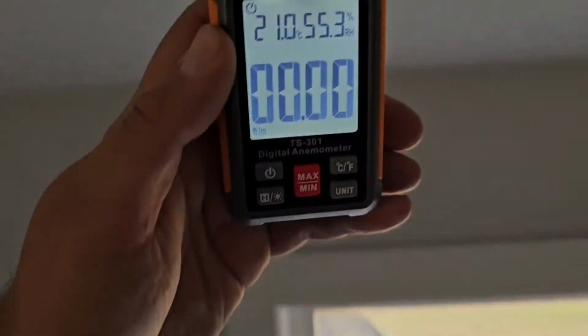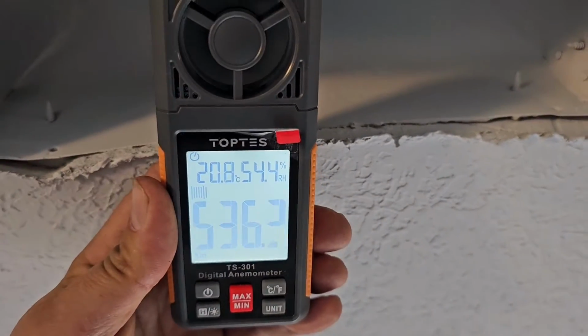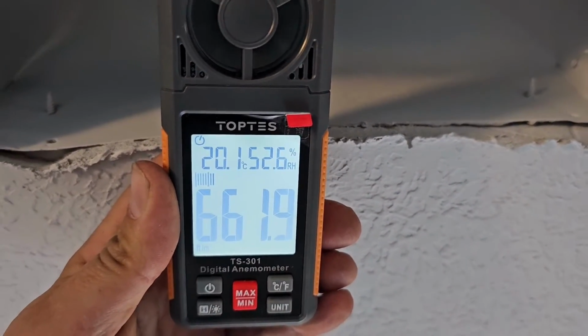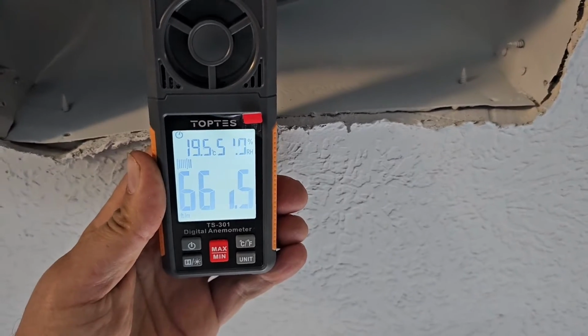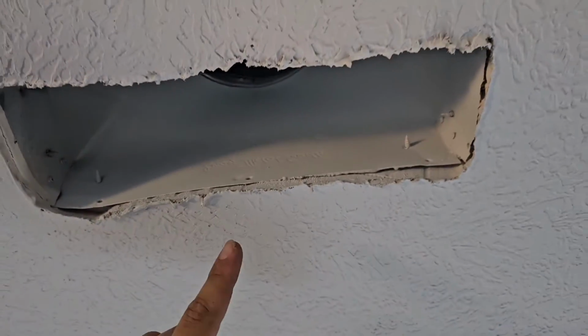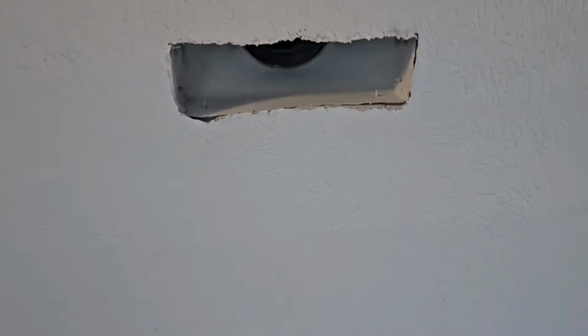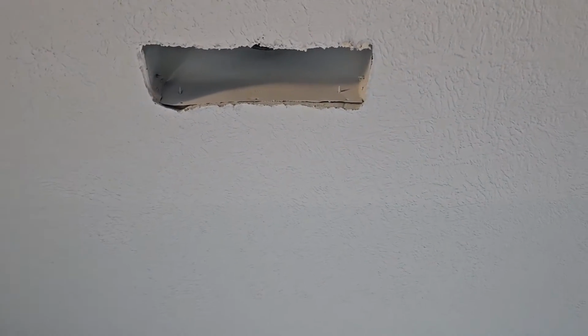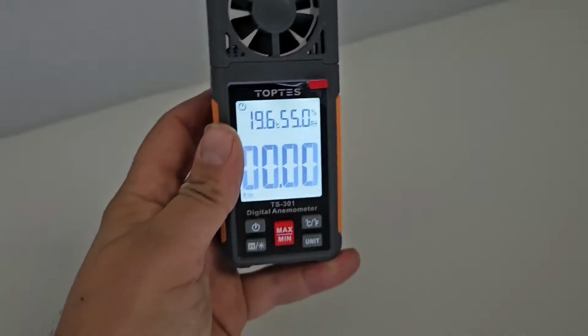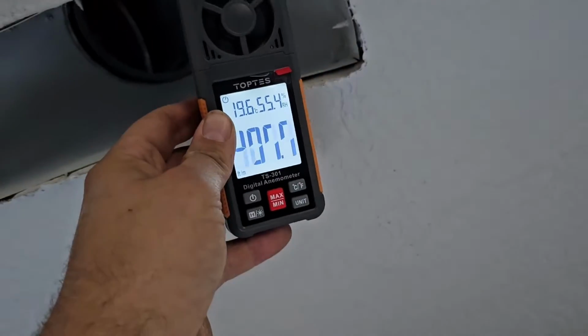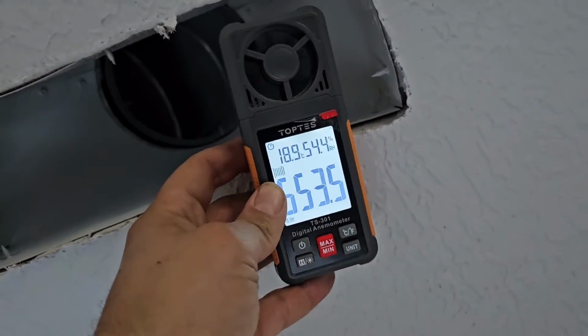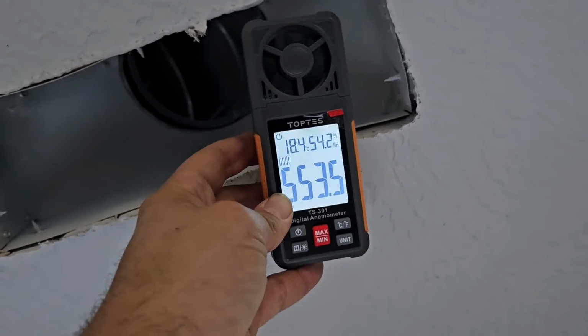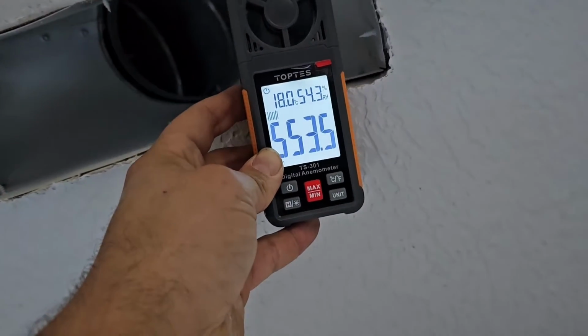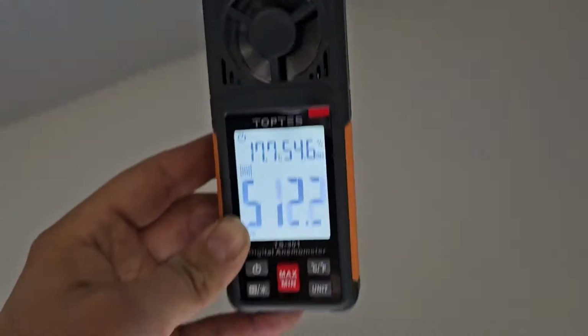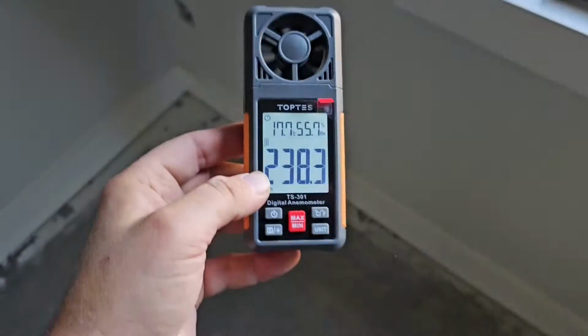Checking the airflow on the upstairs vent. Beautiful, in between 400 and 700. Of course, it'll be better to check it with the actual ceiling grill or vent or register covering that boot. All right, checking the vent downstairs. A little hard to reach. Okay, almost 600. All right, so about 550.